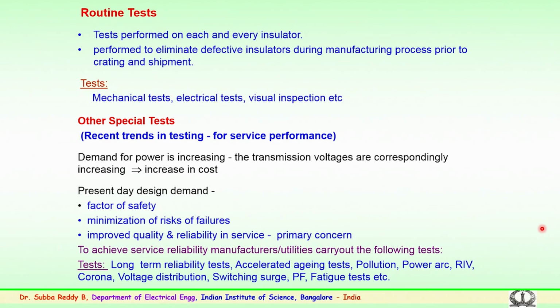Next is the switching surge, which is very important at EHV levels. Switching impulses for voltage levels operating above 400 kV cause the insulation to break down early. So, switching surge tests are normally carried out for all the equipment for the specified levels. Then power frequency overvoltages: during normal working voltage, that is the power frequency working voltage, there could be some disturbance in the transmission network, and overvoltages for a few cycles could be witnessed, which the insulation has to withstand.